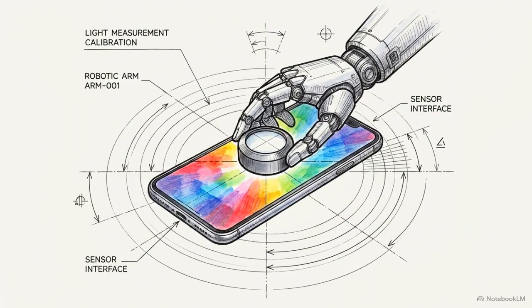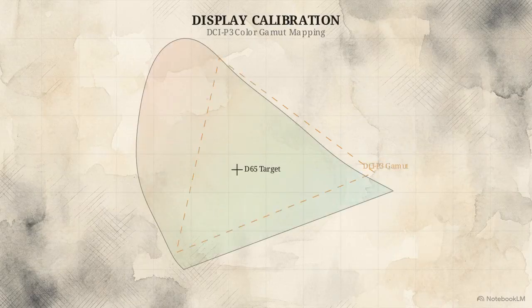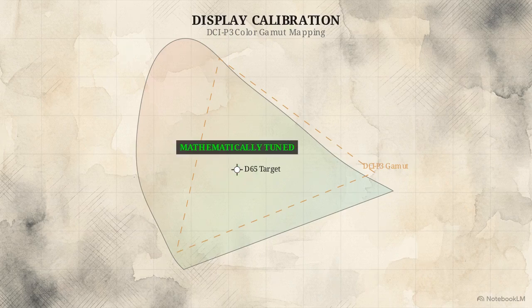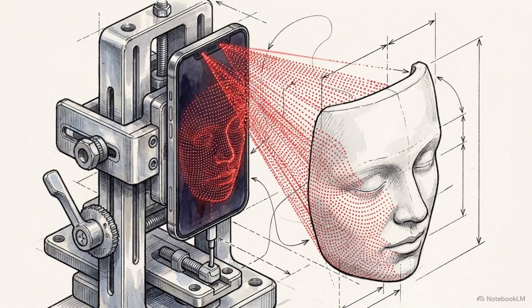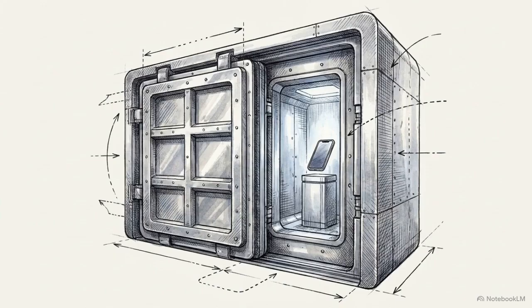Next comes individual display calibration. A colorimeter measures the specific light output of the OLED panel and generates exact correction values, so the screen perfectly matches a wide color gamut standard. Biometric calibration follows. The front-facing projector fires 30,000 infrared dots against a physical reference surface to perfectly map and verify the depth sensor's alignment. Finally, the device enters a shielded test enclosure.